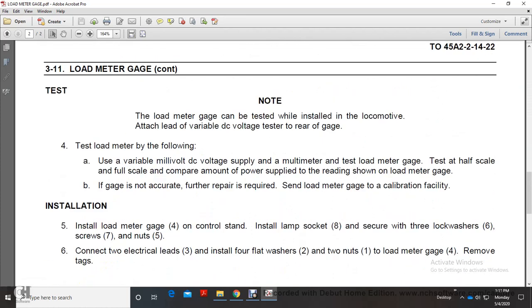Test: note that the load meter gauge is tested while installed in the locomotive. Attach the leads of the variable DC voltage supply to the rear of the gauge. Test the load meter gauge using a variable millivolt DC voltage supply and a multimeter. Test at half scale and full scale, comparing the power supply amount with the reading shown on the load meter gauge. If the gauge is not accurate, further repair is required at the load gauge calibration facility.